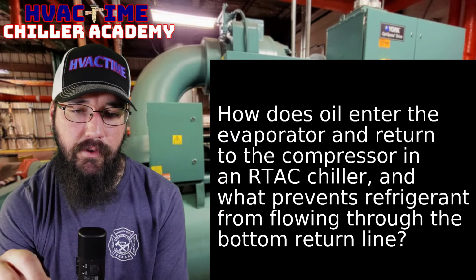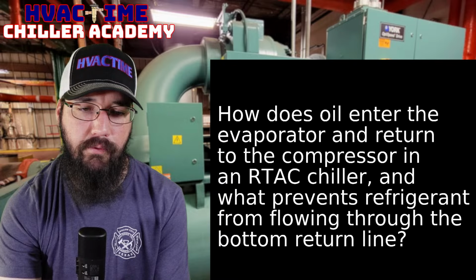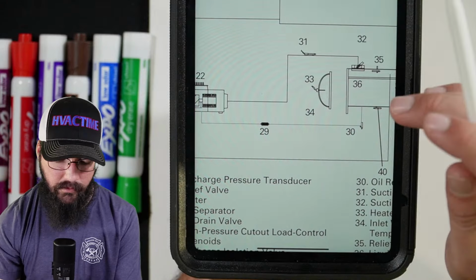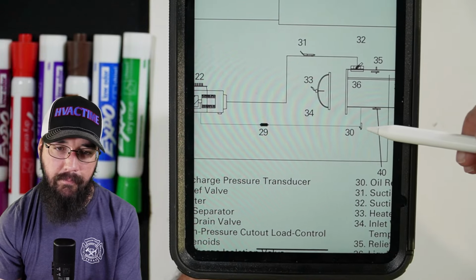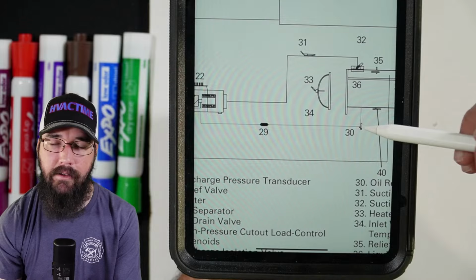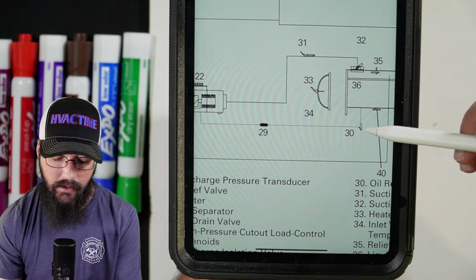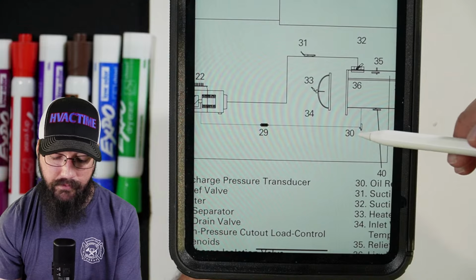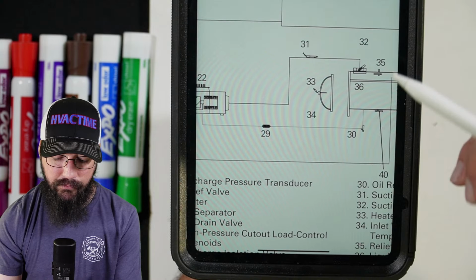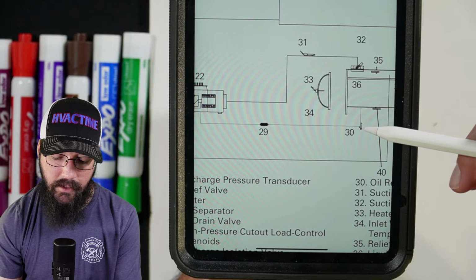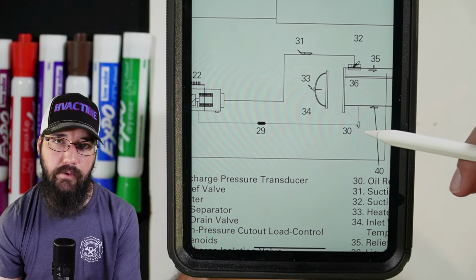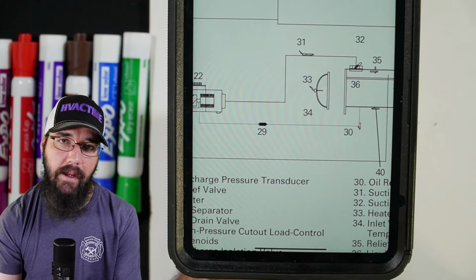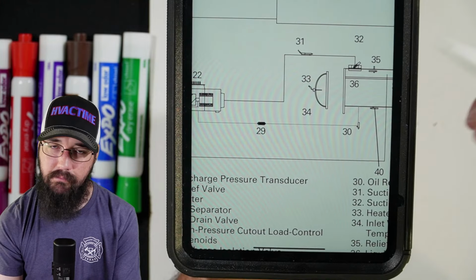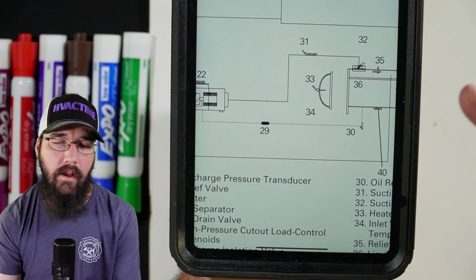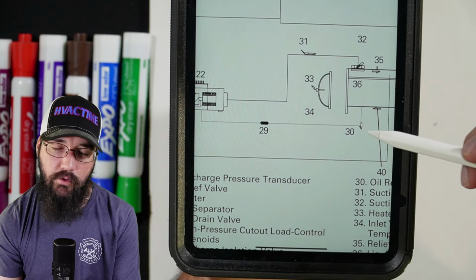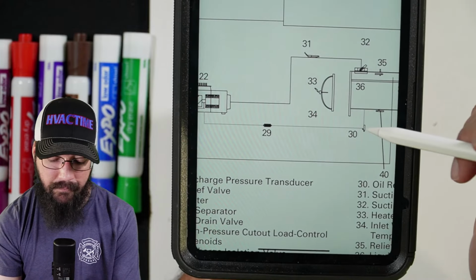And then, what prevents the refrigerant from flowing through the bottom return line? Well, one, this service valve here can fail. If somebody closed it at some point and didn't open it again, or if it's not open, you have to pay attention to where this line is at. I would have to verify by reading a little more, because on a lot of these machines you have to calibrate this valve yourself in the field. These valves aren't made to go full open. They may only be, say, 1 or 2 turns open, and that's how you're able to set flow. So if you open this too much, it could overfeed into the compressor and cause an actual flooding. That's something to be aware of.